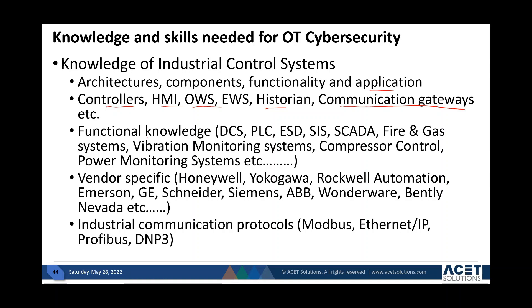You will need to know the functional differences between DCS, PLC, ESD, and SCADA because the cybersecurity requirements are different for each. What is a vibration monitoring system, and what impact will it have if that particular system goes down for an hour?